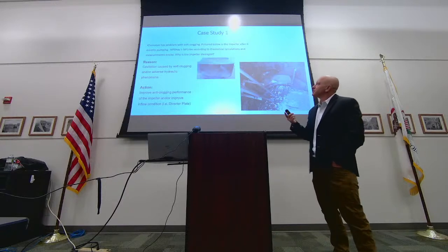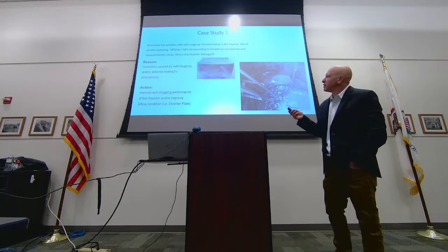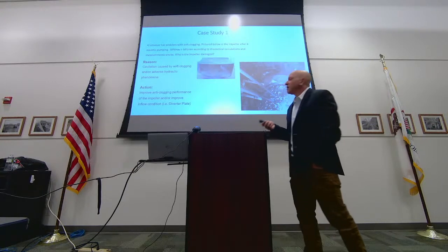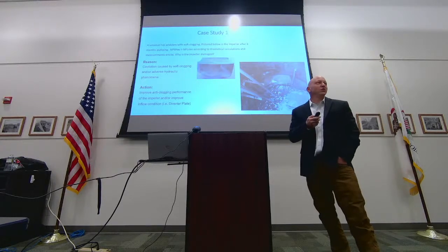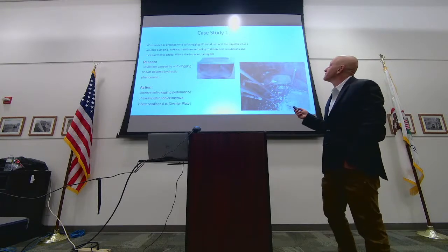Soft clogging. Again, you're having fibrous material getting built up at the inlet and then slowing down the flow. In this particular case, they put a non-clog impeller in and saved the station. Unfortunately, I didn't get to build a whole new station out of it, which is what I wanted to do when I went there. We just changed out an impeller.